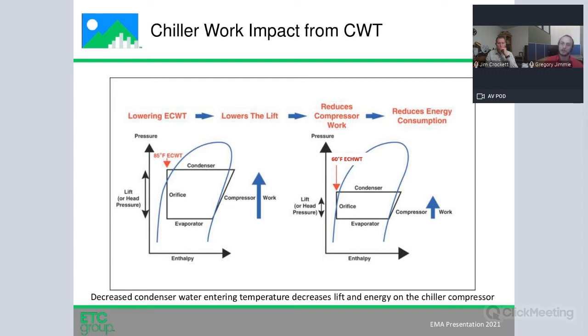For example, with a York chiller, you'd probably think of it in terms of temperature, maybe around 8 degrees between leaving chilled water and leaving condensing water. A Trane chiller may be looking at it more as far as pressure is concerned, maybe, let's say, 4 psi between the two barrel pressures. So you need to have something there to establish some work for that compressor to actually do, and also allow enough pressure for the cycle to continue to actually happen.